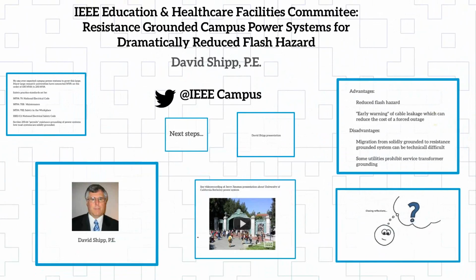When I put it in, do you realize how much money they pay for copper to run 100% neutrals everywhere to use 5% of the capacity? And the economics actually will work out for them if they do it right up front. So I can address the safety, I can give them safety and continuity, and I can borrow from these other industries and retrofit it into your setting. And see, that's what I was trying to do in the hospitals, especially in the emergency rooms, all the rest. Now, the only requirement is a little bit of engineering design.